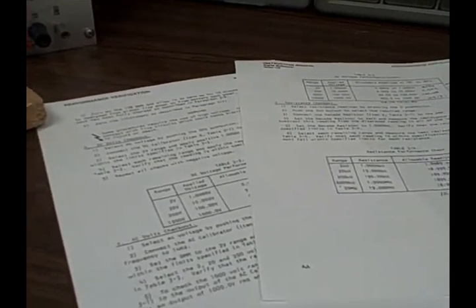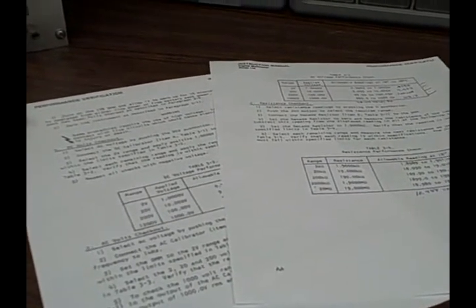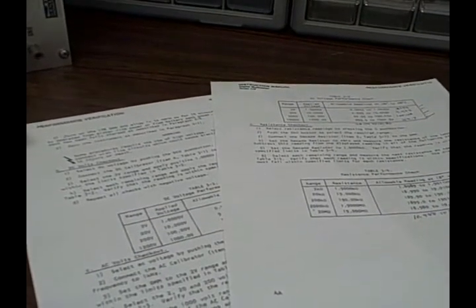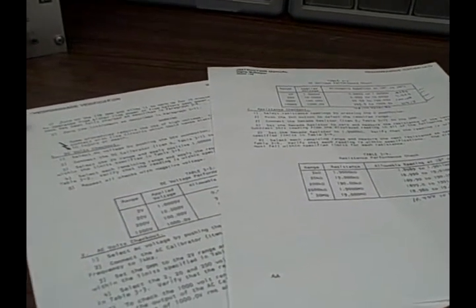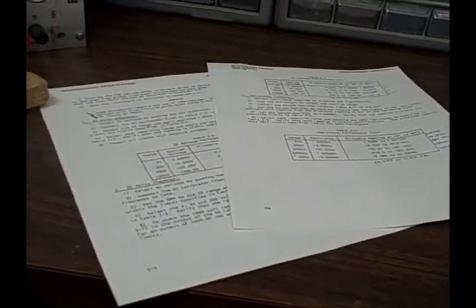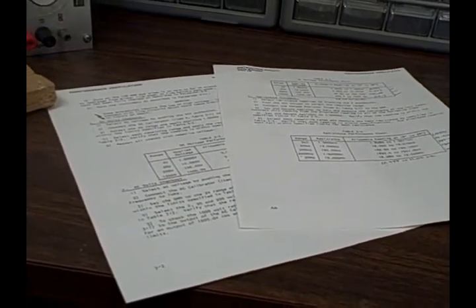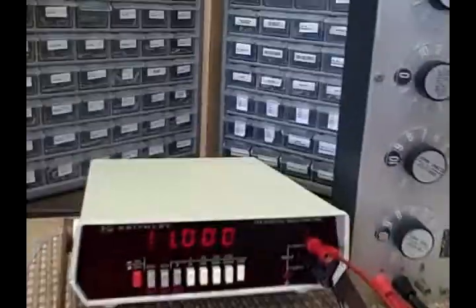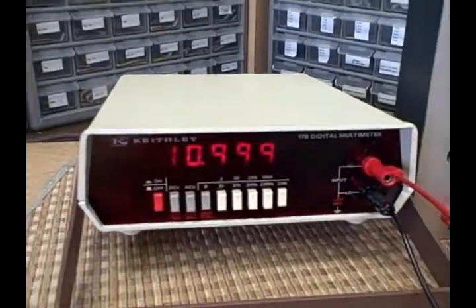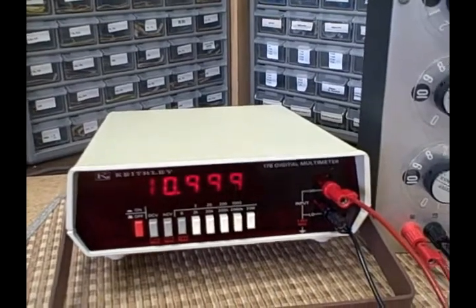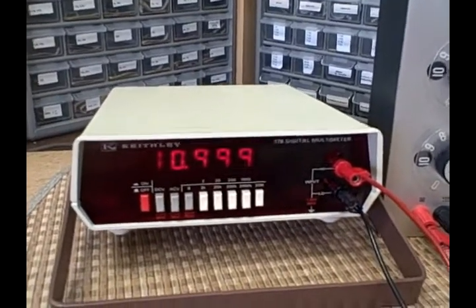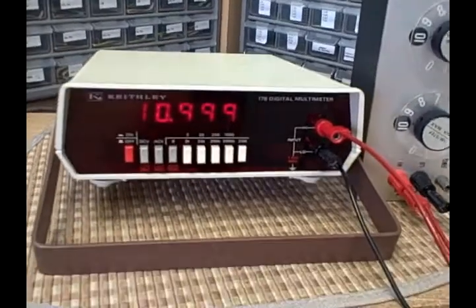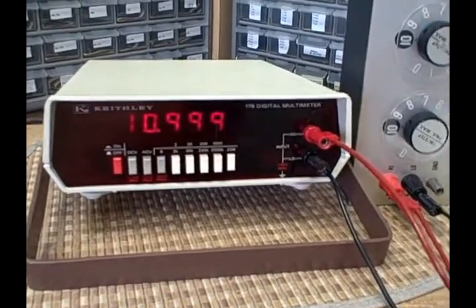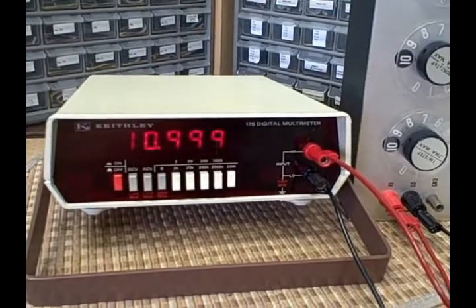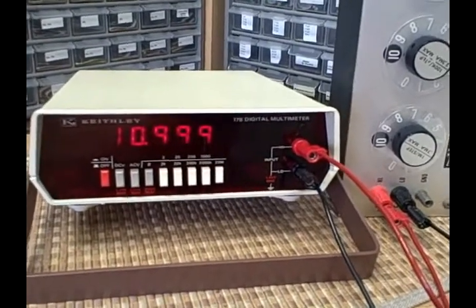Again, we passed the performance test for resistance, so that's the 3 tests. The unit is passing within its allowable readings, and I guess that would be the end of it. I'm going to provide a CD manual for this unit, the operating and maintenance manual. It'll take you through the calibration procedures so that if you ever have to perform a calibration in the future, you can. This calibration here should hold for up to a year. So we're good.